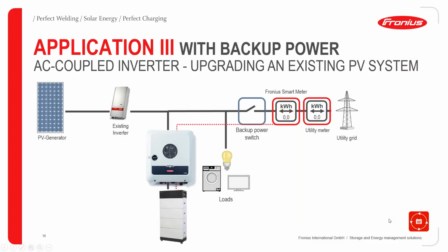And also in such cases, it is possible to have a backup power switch. In this case, you only have to be sure that in backup power mode, that means if there is a grid outage, this existing inverter won't work, because we are then building up an AC grid with 53 Hertz with our Gen 24 Plus device, and that would be a knockout criteria for the existing inverter, because 53 Hertz is just too much.